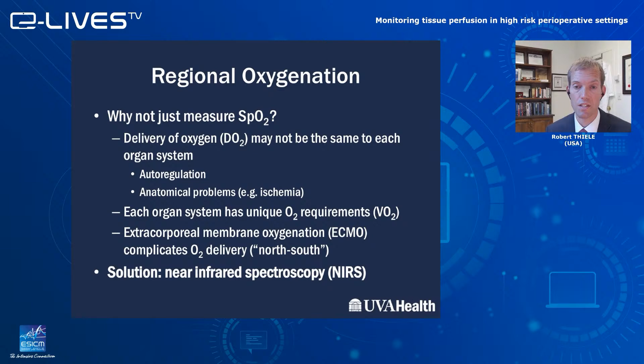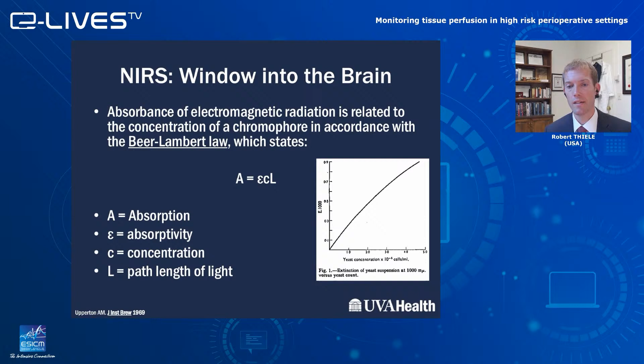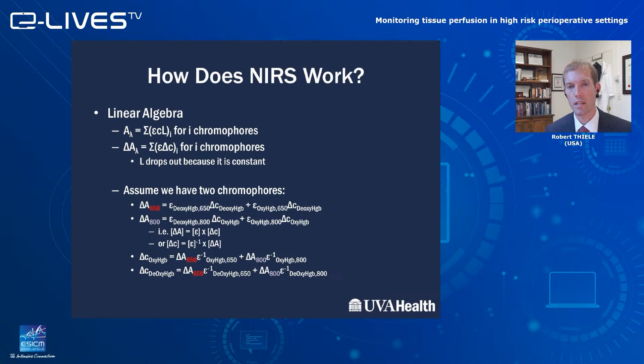So NIRS is really thought of as a window into the brain or any tissue. The absorption of near-infrared light can be described as a concentration of some chromophore, something that absorbs infrared light, its scattering coefficient, and the path length. And you can create a set of equations that will then allow you to calculate tissue saturation as long as you have 2 wavelengths of light. So you need 1 wavelength of light for everything that you're measuring. And it essentially measures the redness, just like the pulse oximeter does. It measures the redness of tissue by comparing the absorption of red light to the absorption of infrared light.